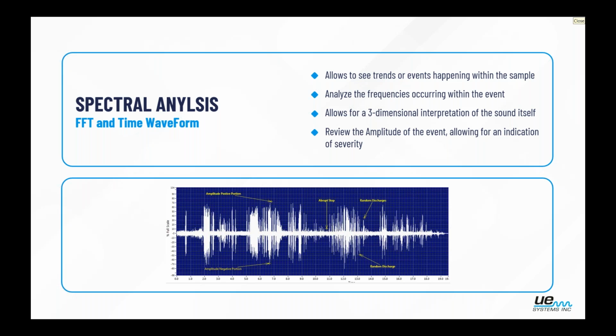So what we're doing when we record those sound files, just to touch on this, is we're going to record that sound, like I said, at 20 seconds or so, and look through it with spectral analysis. We're looking at it in two different forms: the event over time, and then the frequencies that make up this sound. So we're able to see the trends happening in the event or events occurring within the sample, to identify, like I said, corona, tracking, arcing, something mechanically loose. We can also look at the frequencies. By breaking it into these two different forms, we're giving that sound a three-dimensional interpretation, so we can be accurate on what is going on and look at the severity of it.